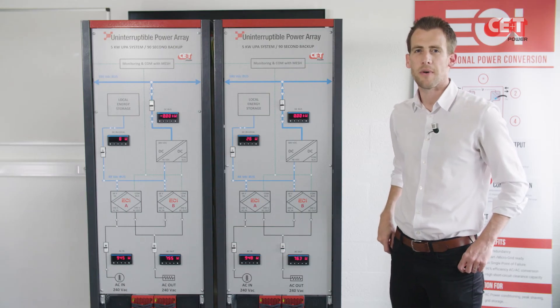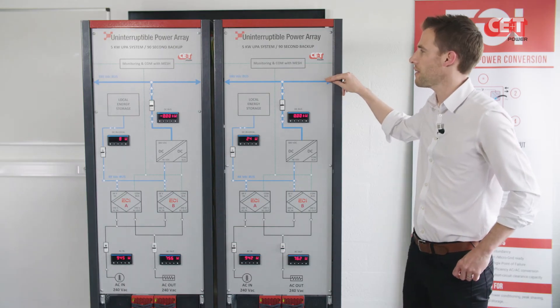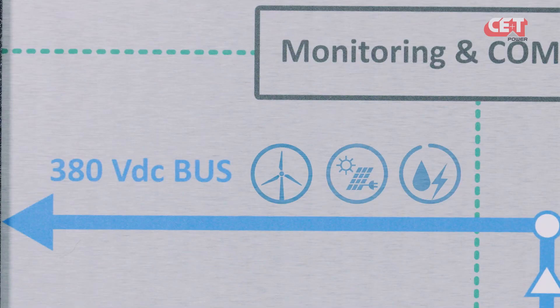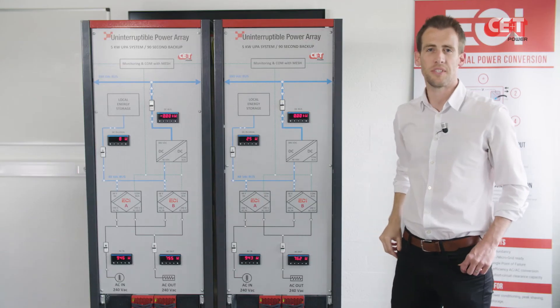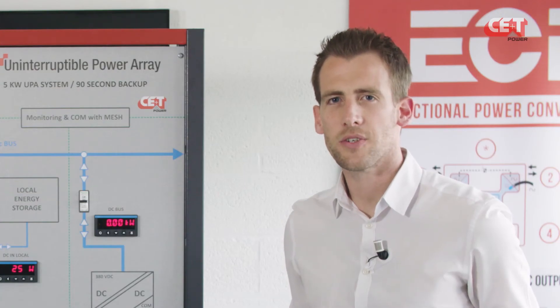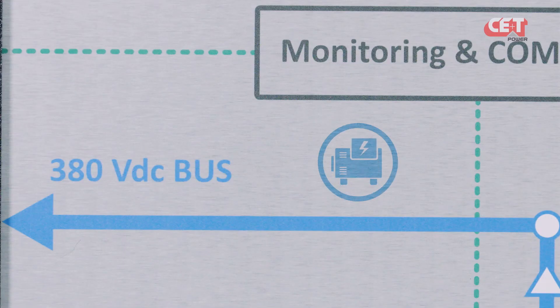Another advantage of the DC bus is that if you have any power source available, such as wind turbines, photovoltaics, or hydroelectric, you can directly plug them to the DC bus. Our intelligent software will manage the sources to reduce the power taken from the grid. You can also add a genset to the DC bus through rectifiers — no need for synchronization.